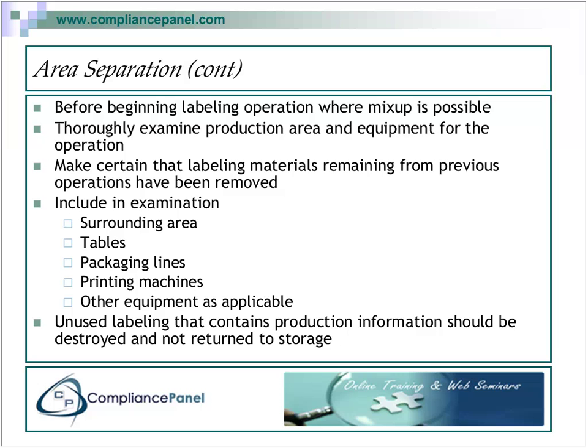You'd be surprised how often people overlook the table next to them for their evaluation of area separation. Any unused labeling that contains production information: perhaps you're going to make 1,000 of these consumables with lot number 123, and label control made a mistake. They issued too many labels, so you have 5 extra labels that say lot number 123. Don't return that to storage. Tear those up because they contain production information that should not be available.